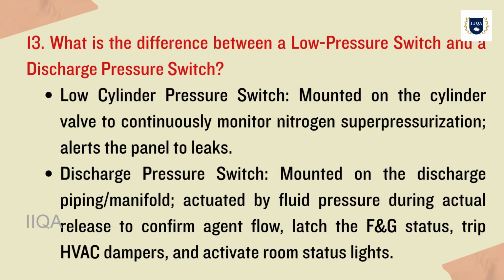13. What is the difference between a low pressure switch and a discharge pressure switch? The low cylinder pressure switch, mounted on the cylinder valve to continuously monitor nitrogen superpressurization, alerts the panel to leaks. The discharge pressure switch, mounted on the discharge piping manifold, is actuated by fluid pressure during actual release to confirm agent flow, latch the F&G status, trip HVAC dampers, and activate room status lights.